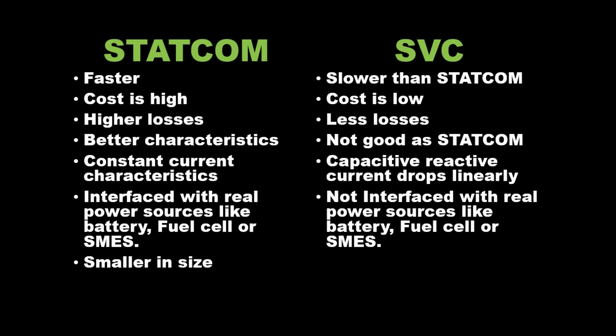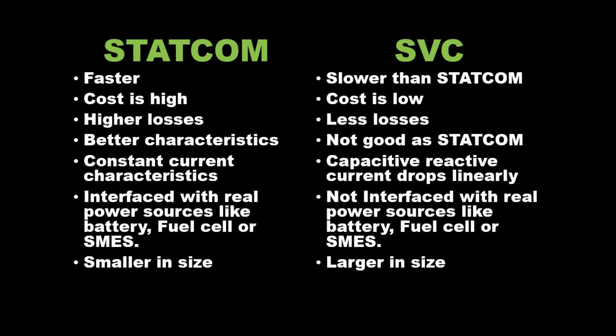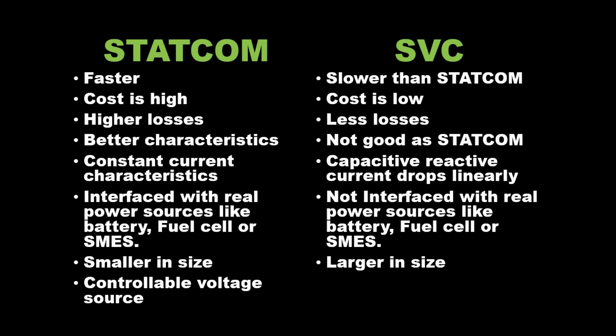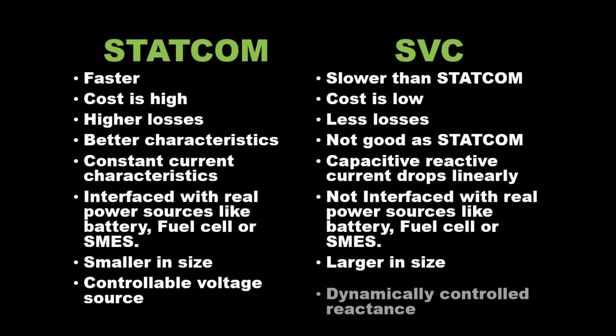StatCom is smaller in size because it does not contain a bulky reactor, whereas SVC is larger in size because it contains a reactor, capacitor, thyristor valve, etc. The operation of StatCom is like a controllable voltage source, while the operation of SVC is like dynamically controlled reactance.